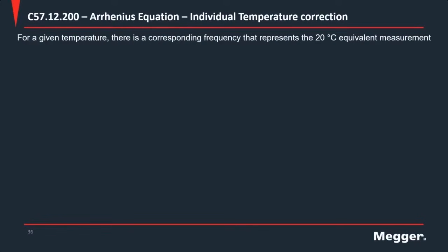And when we use that information, what we find is that for a given temperature, say if we're testing outside and it's 30 degrees C, we know that there is a frequency that we can measure at that corresponds to the 20 degrees C measurement. So instead of measuring at just 60 hertz, we might measure at 60 and 150 hertz. And that will give us our hot temperature correction. If we're testing at 10 degrees C and we want to get back to 20 degrees C, then we would measure at, say, 30 hertz. And that would be the 20 degrees C measurement.